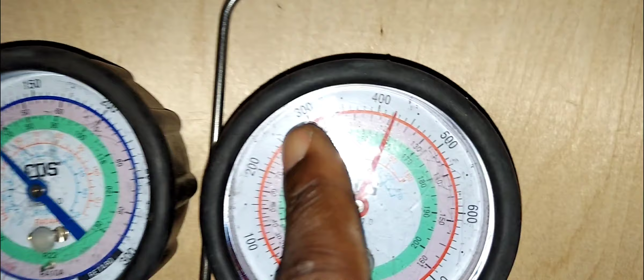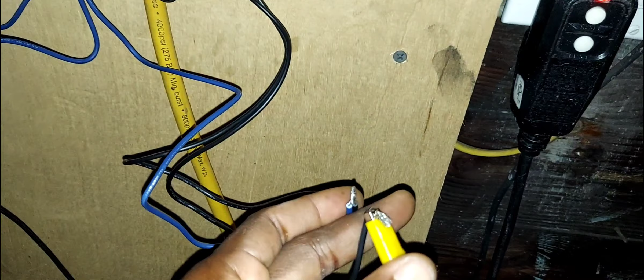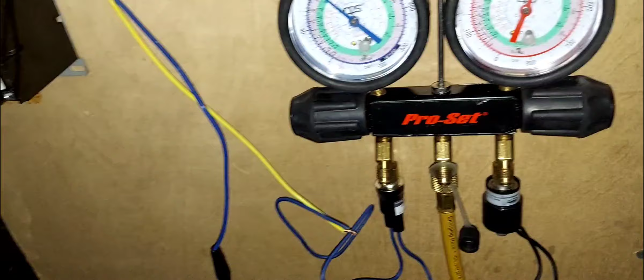Okay. So the first thing I'm gonna show you is how to bypass it, how to bring your compressor back on, and simply, just like the low pressure switch, you take the two wires on the switch and touch them together. Come on, what's going on here? Now, can you imagine bypassing your high pressure switch and starting your compressor while the head pressure is 400 plus psi? You could ruin the compressor, blow the fuses, ruin the contactor because there's going to be a lot of amperage draw, blow out the compressor terminal and hurt yourself, burst your coil. A lot of problems could happen from bypassing the high pressure safety switch. It's very dangerous. I wouldn't recommend it.